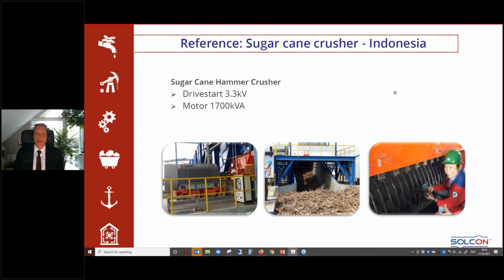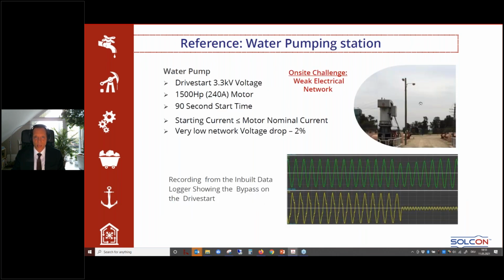Sugarcane crusher is an application from Indonesia. 1700 kVA motor, 3.3 kV. The sugarcane hammer crusher, as you see here, is demanding from the torque point of view, not so much because it is running up empty, but it is giving you a hell of a long starting time. And this is why the Drivestart was used here.